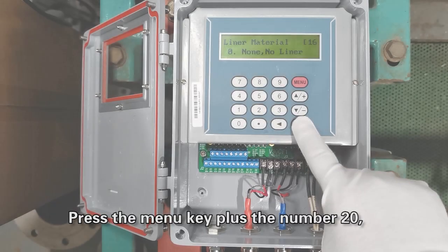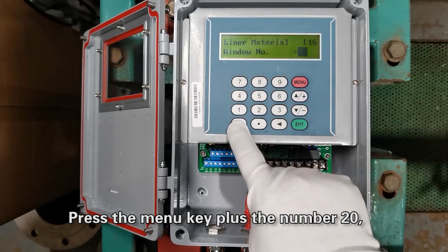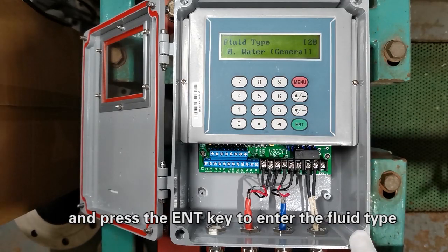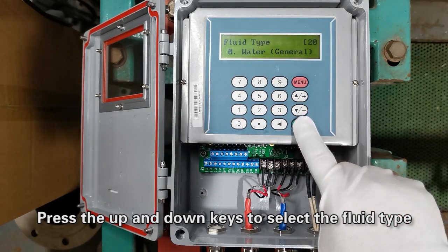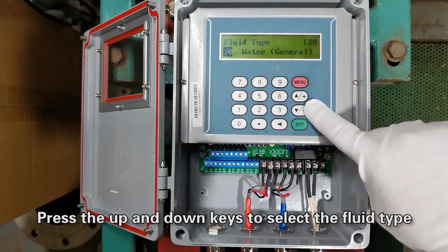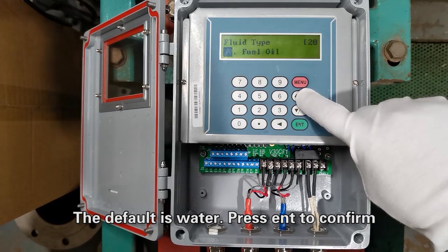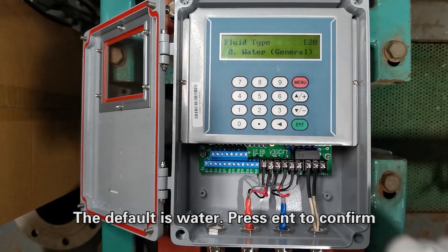Step 7. Select fluid type. Press the menu key plus the number 20 and press the Enter key to enter the fluid type. Press the up and down keys to select the fluid type. The default is water. Press Enter to confirm.